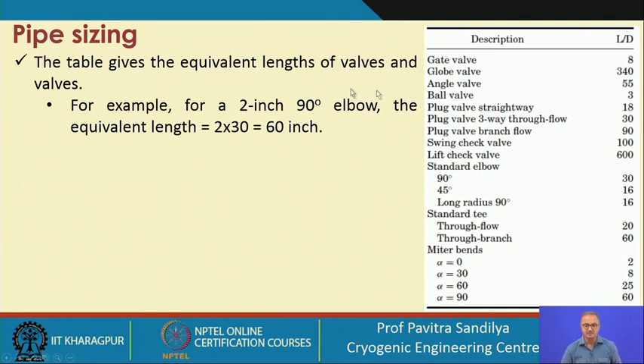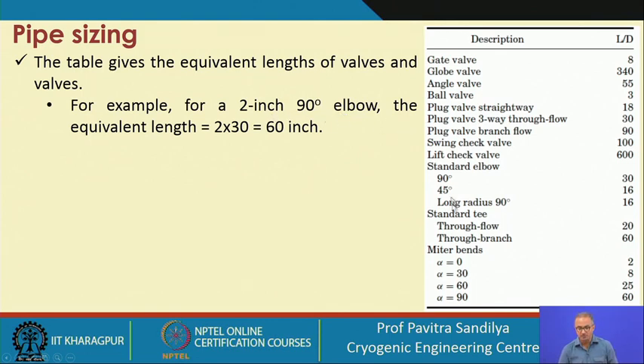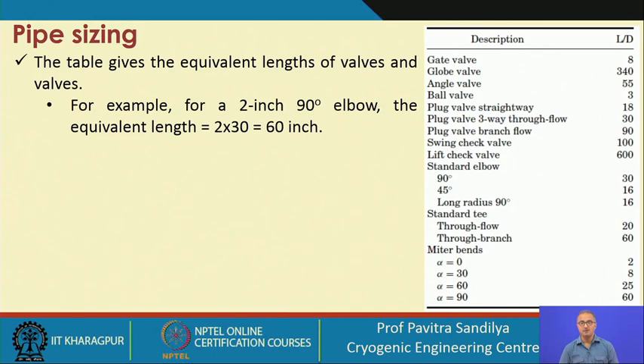A table gives equivalent lengths for valves: gate valve, globe valve, angle valve, and various other valves and fittings. Depending on the type of valve or fitting chosen, there is an equivalent straight pipe length. For example, a 2-inch 90-degree elbow has an equivalent L/D ratio of 30. Multiplying by 2 inches gives an equivalent length of 60 inches — meaning the pressure drop across a standard 90-degree elbow equals that of 60 inches of straight pipe of the same diameter.